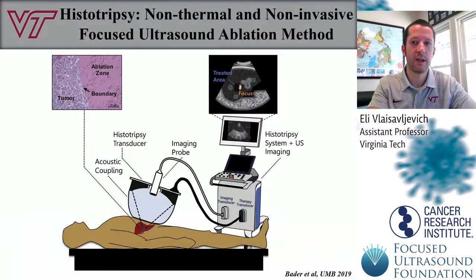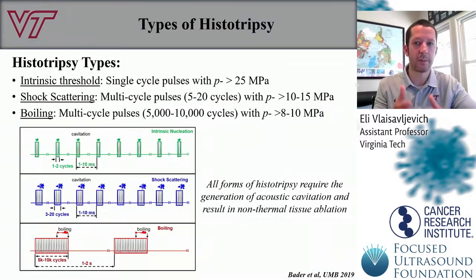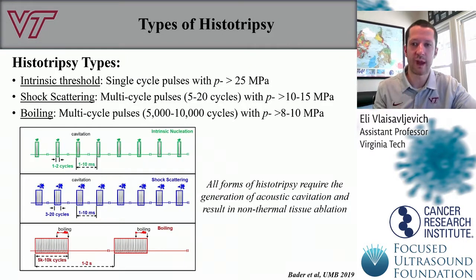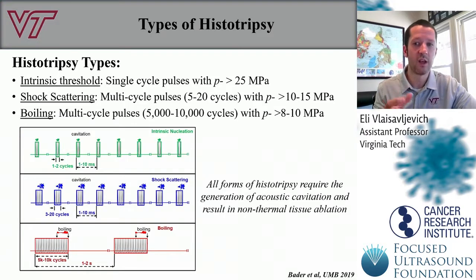Next, we're going to change gears and talk about histotripsy. Histotripsy is a completely non-invasive and non-thermal ablation method that uses focused ultrasound to generate a cavitation bubble cloud, which results in the mechanical ablation of tissue into acellular debris with very high precision. There are three different types of histotripsy: intrinsic threshold histotripsy uses single cycle pulses at very high pressures greater than 25 MPa peak negative pressure; shock scattering uses multi-cycle pulses between 5 and 20 cycles with peak negative pressures of about 10 to 15 MPa; and boiling histotripsy uses much longer pulses with slightly lower pressure to rapidly heat the tissue and generate a boiling bubble. All types use very low duty cycles to avoid any thermal damage to the tissue.